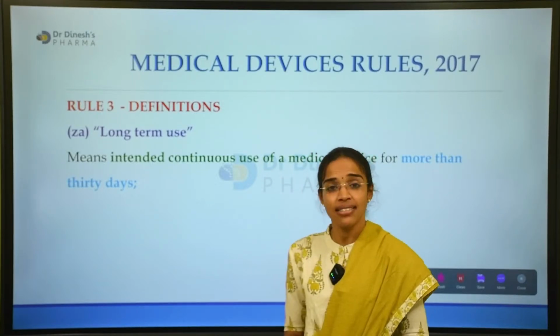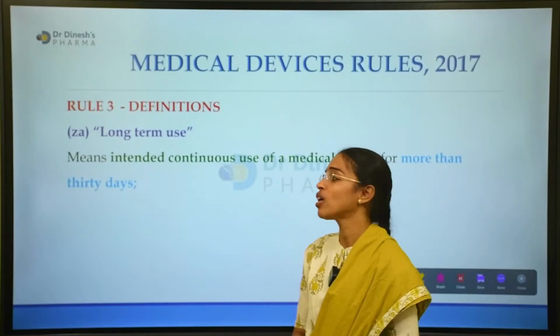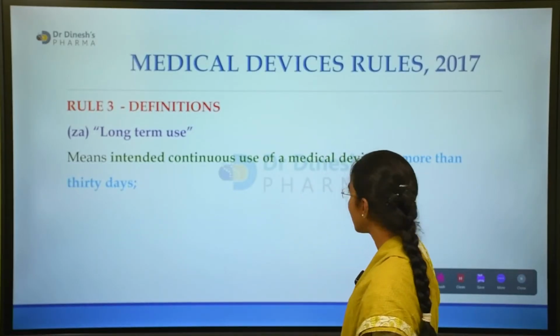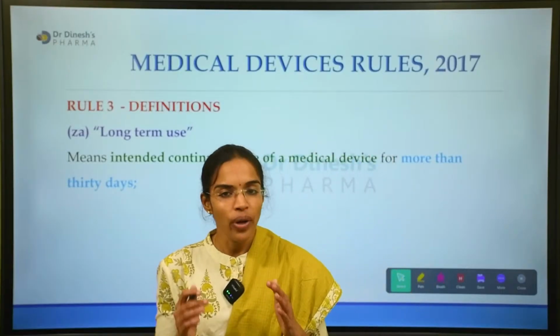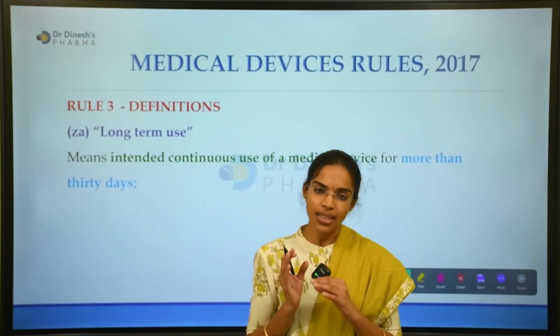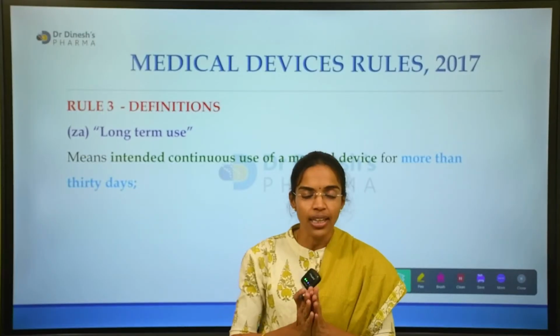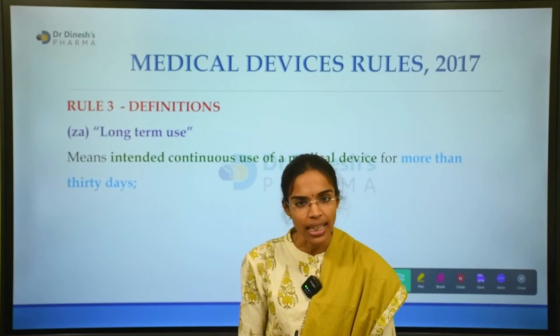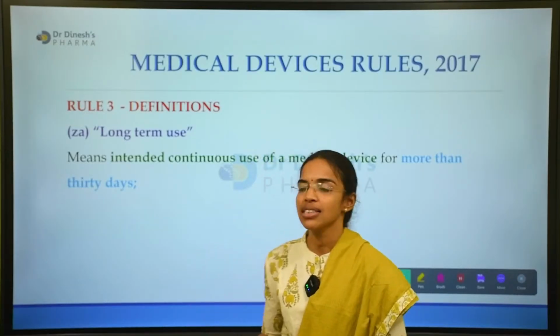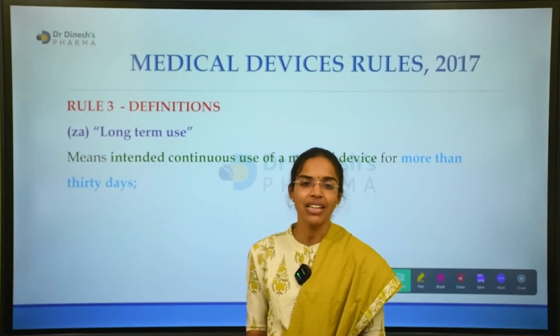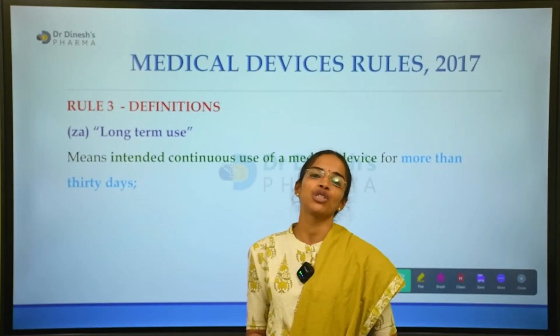3ZA is nothing but about the long-term use. What is the long-term use? The intended continuous use of a medical device for more than 30 days. When a particular medical device is intended to be used continuously for more than 30 days, then that can be considered a long-term use medical device.